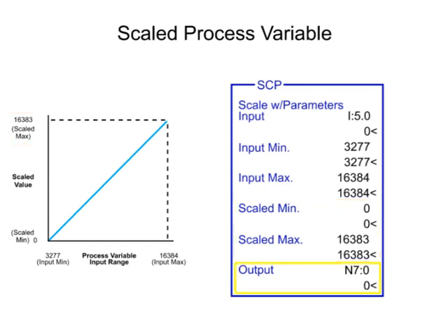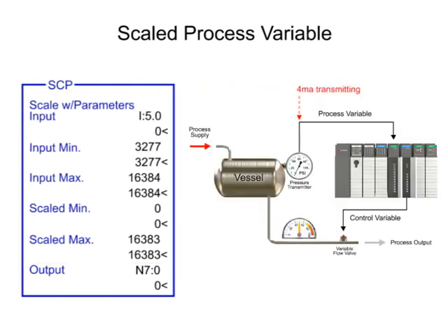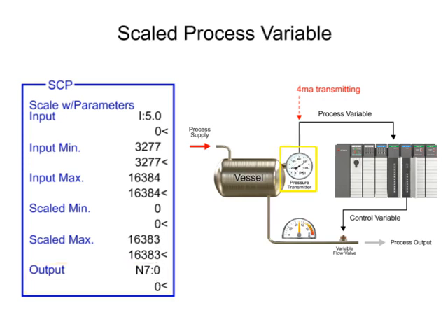The SCP output parameter is the integer file address where the scaled output is stored and then used by the PID instruction as the process variable. For example, when the minimum pressure of 0 PSI is measured, a scaled value of 0 is transferred to the SCP output, and when 100 PSI is measured, a scaled value of 16,383 is transferred to the SCP output.